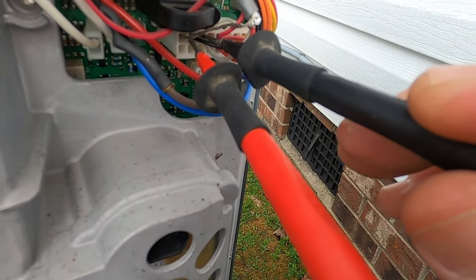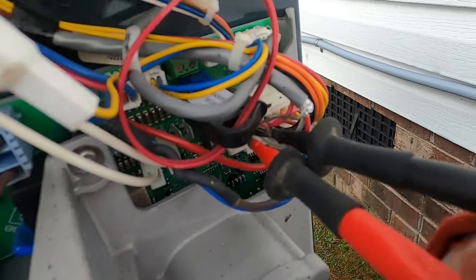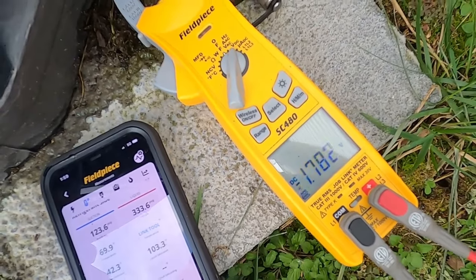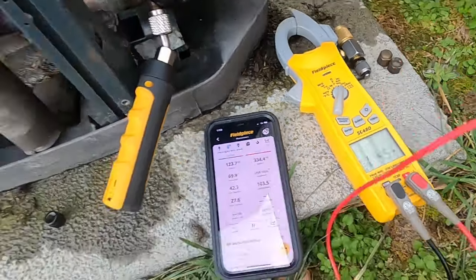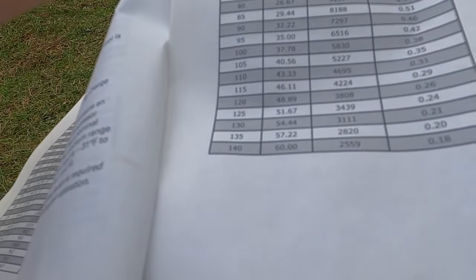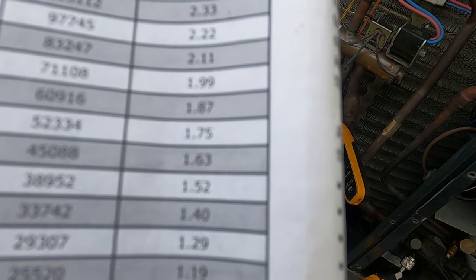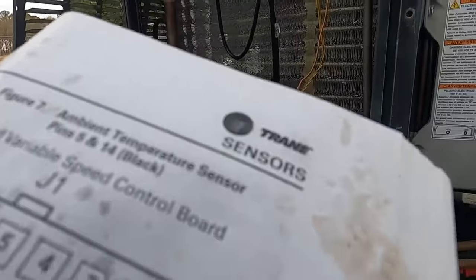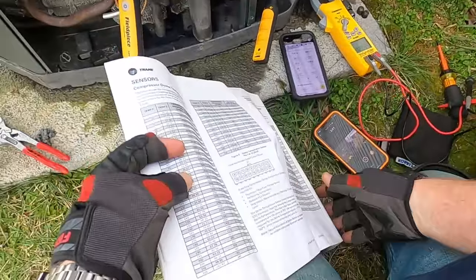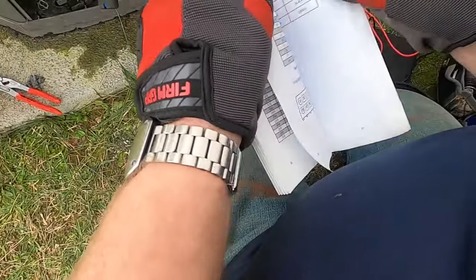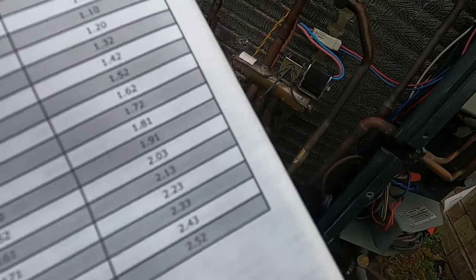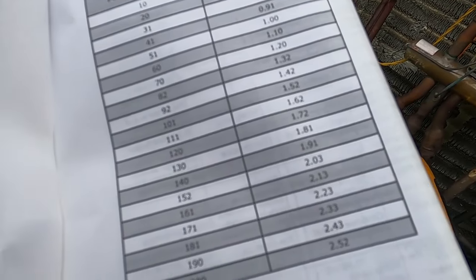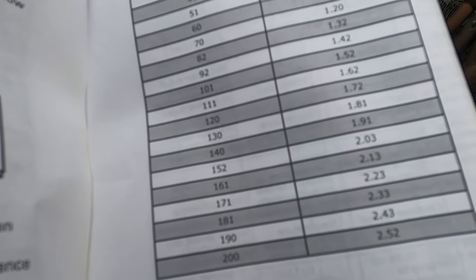against this white wire. I'm getting 1.7. You look at that, 1.7 volts DC right there. So according to our chart, 1.7 volts DC. Well, how about I look at the right chart, guys? Damn, I'm having one of those days. Suction pressure transducer is this chart. One of those days, guys. 1.72 volts DC is 120 psi. We're running at 128 right now.